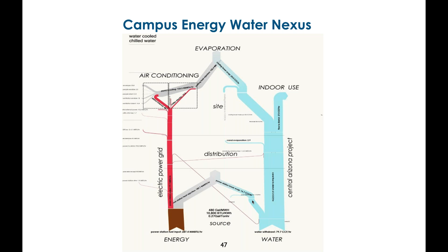The power coming into campus goes two places: one to the chiller plant, running the chillers and towers, and the other feeding the internal loads of the buildings, like lights, computers, elevators, whatever the electric demands are, which end up being heat loads for the building air conditioning system. On the far left are the other components of the heat load, the envelope, the people, the ventilation, all combined into the energy we have to pull out.